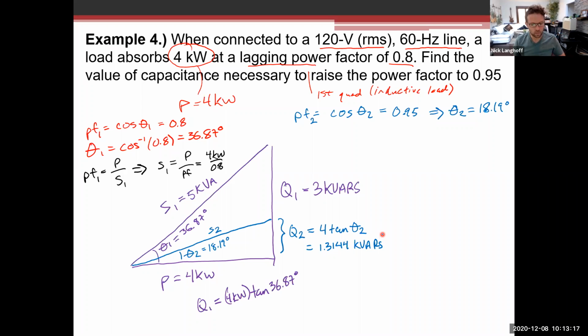We've been asked to find how much capacitance is necessary to raise the power factor to 95%. We know that corresponds to a power factor angle of 18.19 degrees. The real power needs to remain the same, since the real portion is associated with the resistive part of the load. It's going to absorb 4 kilowatts no matter what.